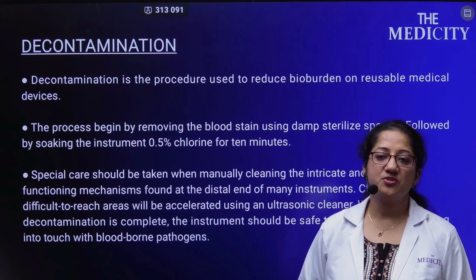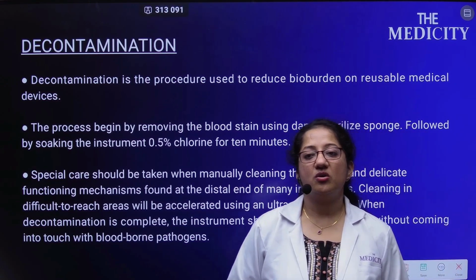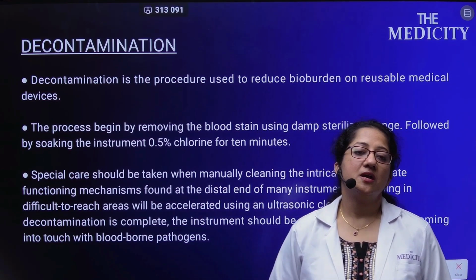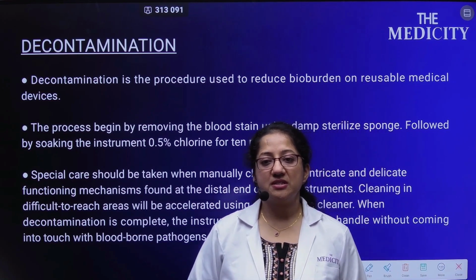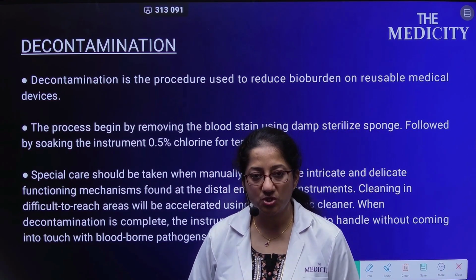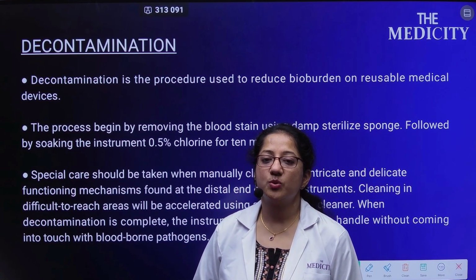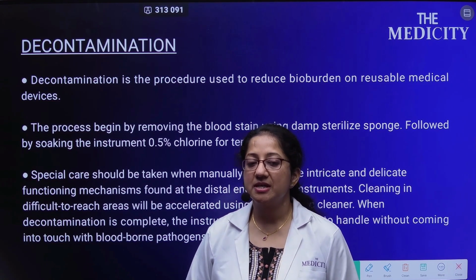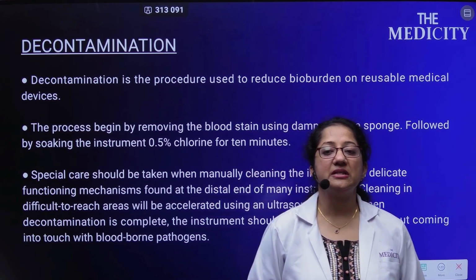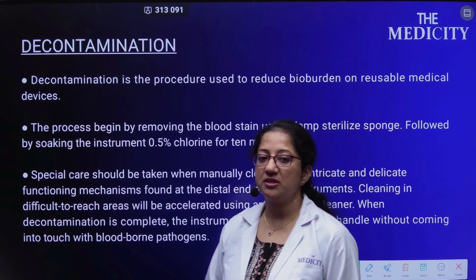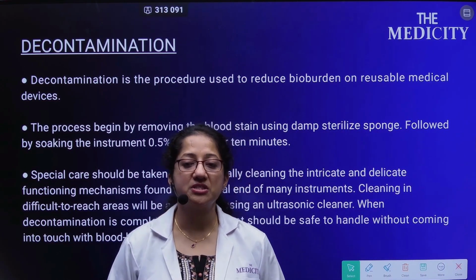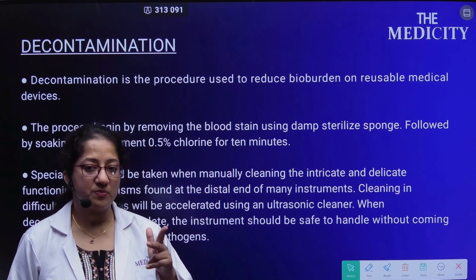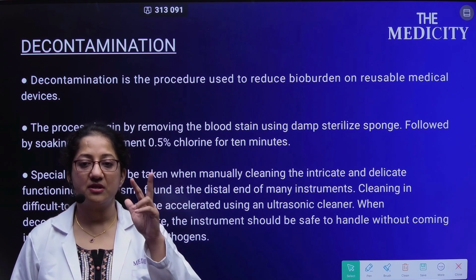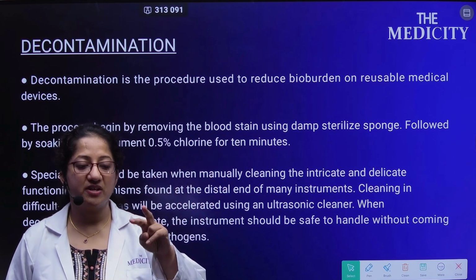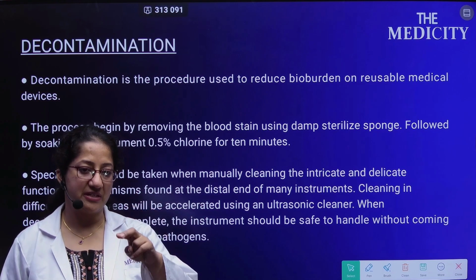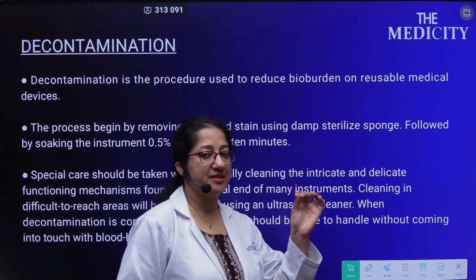Decontamination is the procedure which reduces the bioburden on the reusable medical devices. The process begins by removing the blood stains using a damp, sterilized sponge, followed by soaking the instrument in 0.5% chlorine for 10 minutes. Special care should be taken when manually cleaning the intricate and delicate functioning mechanisms found in the distal end of the instruments. The laparoscopic instruments have a very delicate edge, that is, the part where we hold the tissue is very delicate. So if we mishandle it, it can get broken.